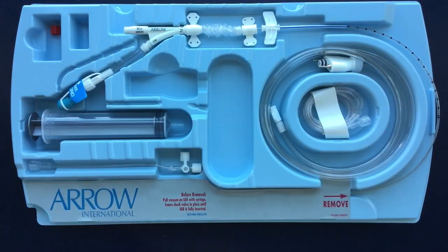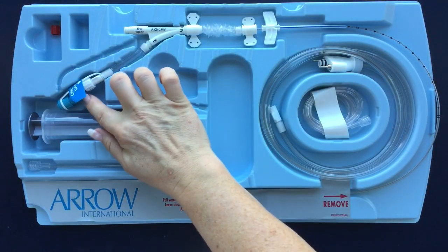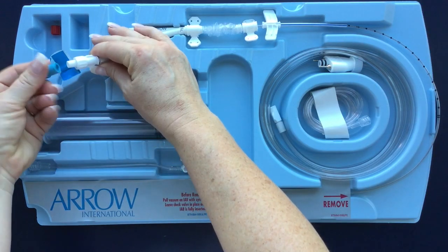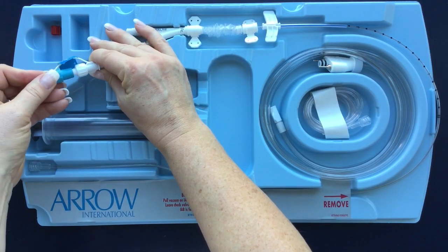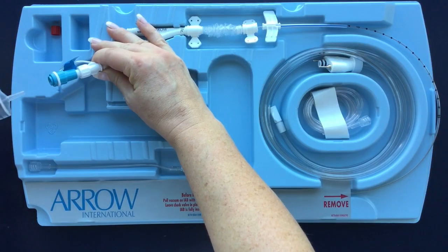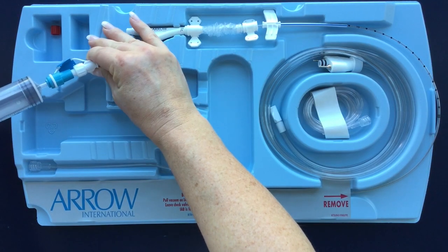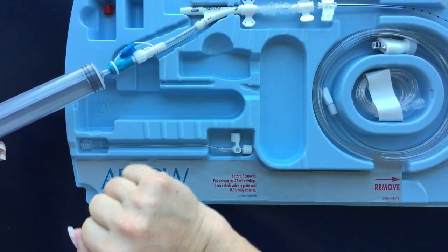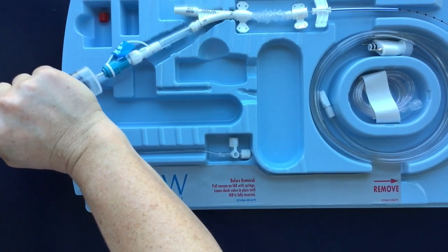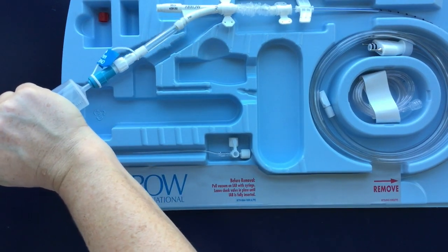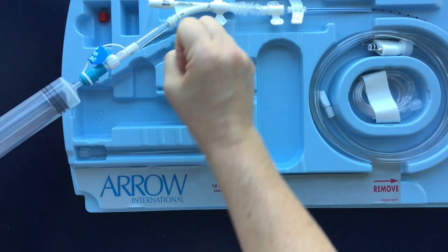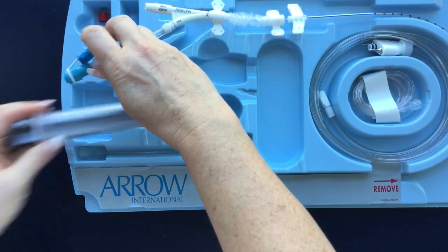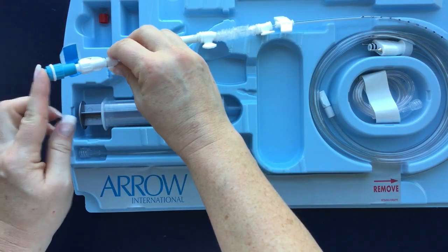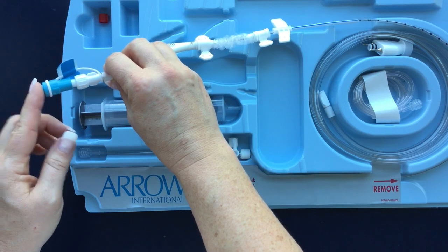To prep the balloon, first I'm going to connect my one-way valve to the helium driveline, and it simply pushes on. I'm going to use a 60 cc slip tip syringe in the kit, connect to the one-way valve. Now I'm going to pull full barrel on the plunger of that syringe and let it come back down into the barrel, carefully disconnecting and ensuring that the blue one-way valve has stayed connected.